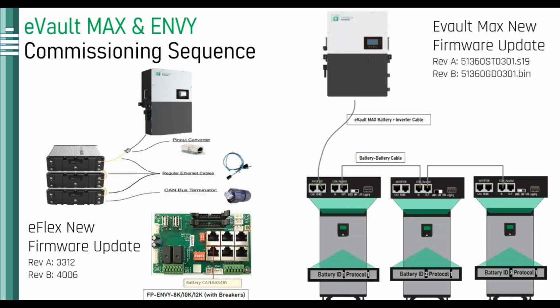And then, once we have connected all the electrical connections on the ports, now we're beginning to wire the system so we can make closed loop communications either with our eFlex or with our eVault MAX, right? So in the case of the eFlex, starting with the commissioning sequence, the ENVY inverter, let me stipulate this, right? The ENVY inverter is a new product, right? And it is very simple, a plug and play. You don't need to do any cable modifications. It's just connecting the cables that come with your battery directly into the designated communication port, as right here in the 8K or 10K.